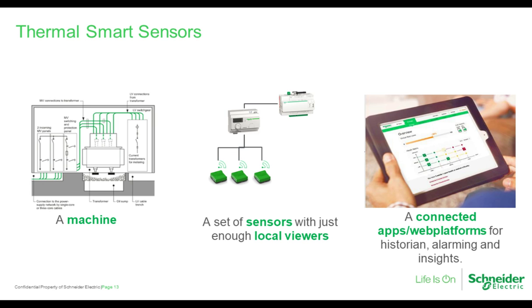We can also add thermal sensors, smart sensors. These smart devices can be added to the electrical system for monitoring system conditions. I know a lot of us use thermographics at this point, infrared scanning to look at hotspots. These new sensors can be embedded within the gear and look at hotspots throughout the gear and send digital communication back to a software to monitor.